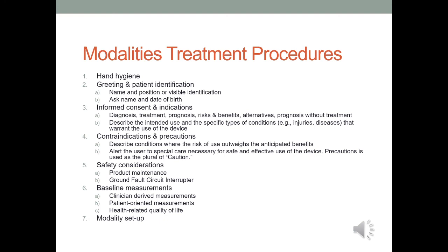And then for all electrical modalities, you need to make sure that the modality is connected to a ground fault circuit interrupter. There's more about that in class, but basically this is a special type of circuit. If you've seen those outlets with the little red and black buttons, that's a ground fault circuit interrupter, or a GFCI or GFI.